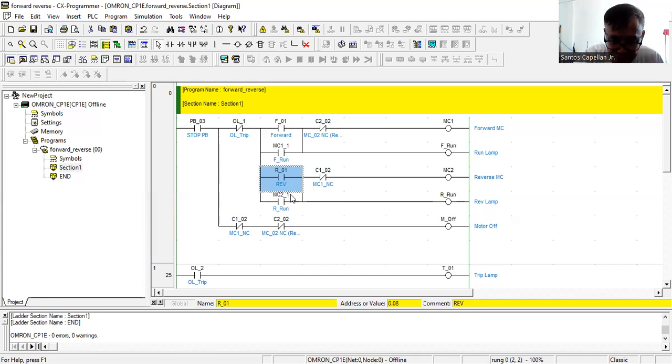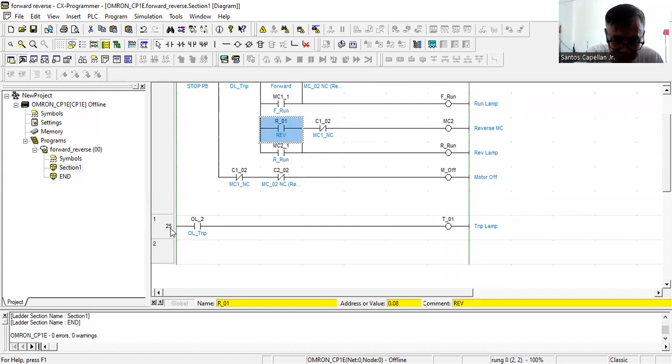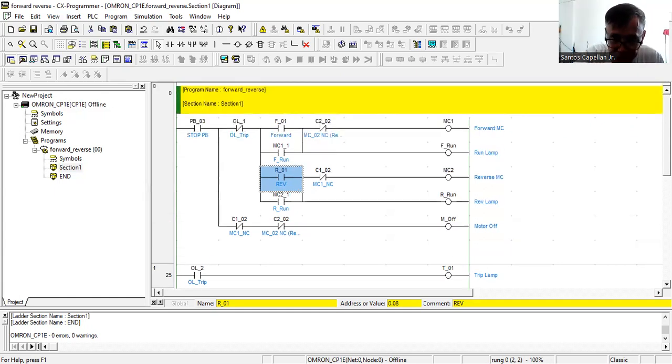Then again, this is the latching. Now, I have here my motor off. Okay, if you remember the electrical circuit diagram that I have shown you in the previous tutorial, this is the one representing the motor off indication lamp. Okay, then the trip in my rung number one, I'm using the trip. In my overload protection, there is a normally open contact. When it closes, because there is a trip condition, then it will drive my coil or my trip lamp.